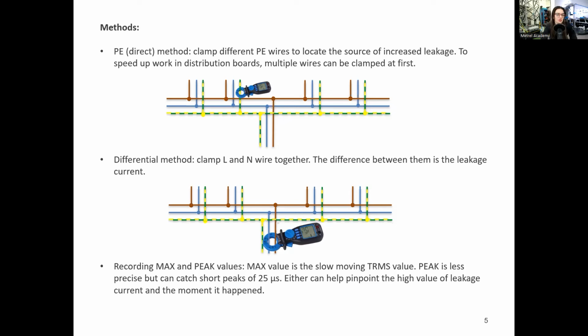Now, both of these measuring methods can be combined with the clamp's basic recording abilities. So we're talking about recording the max values to find any slowly rising peaks of leakage current, while the peak value is less precisely measured, but it can catch very short peaks down to about 25 microseconds.